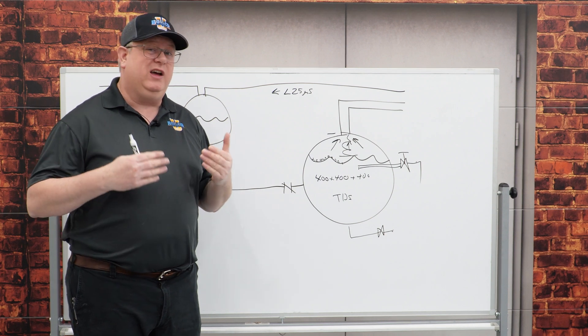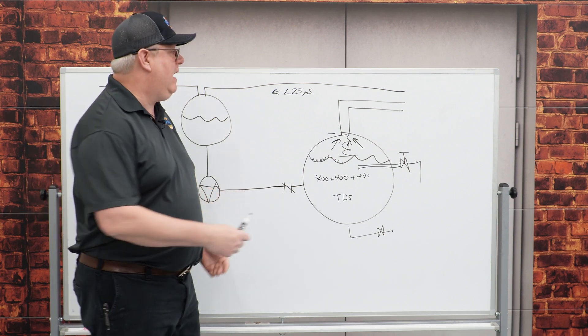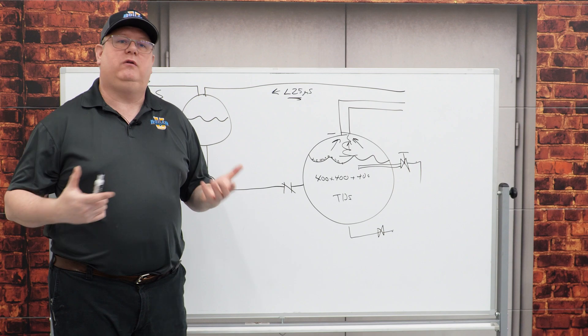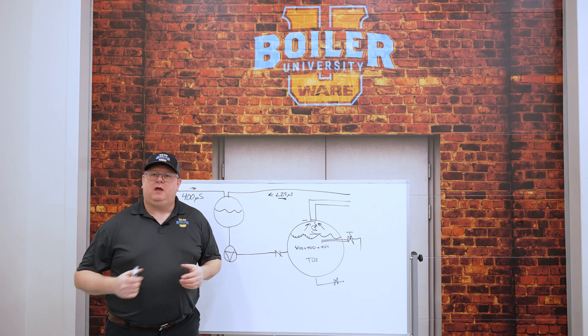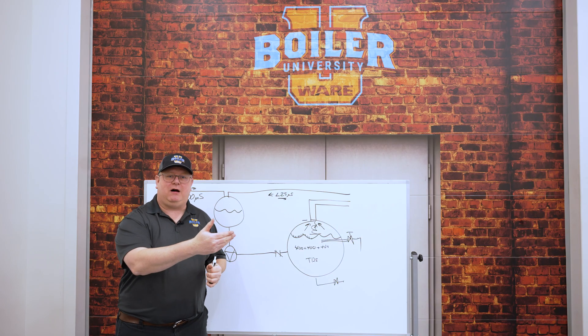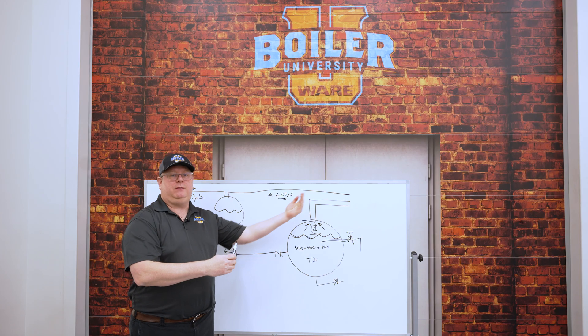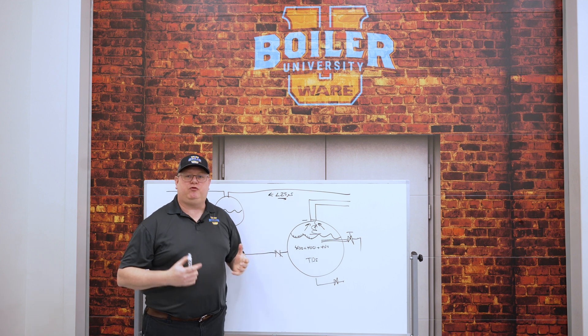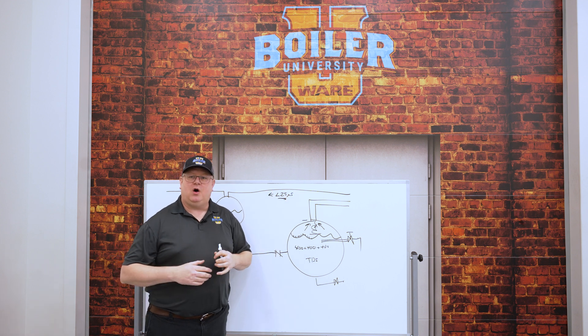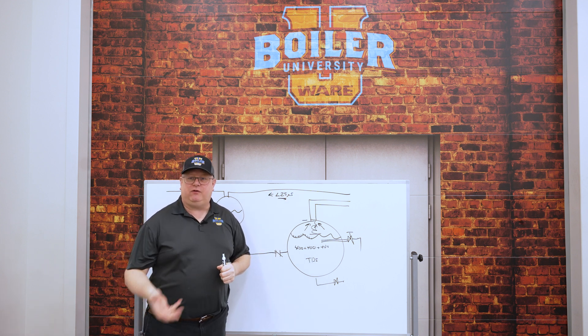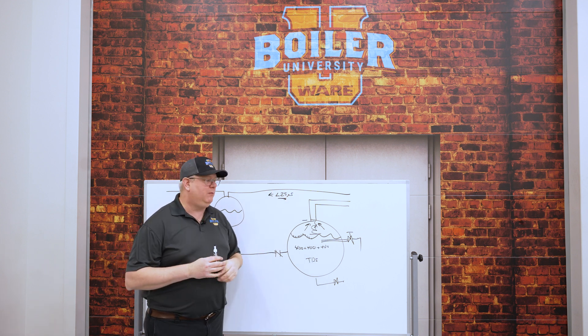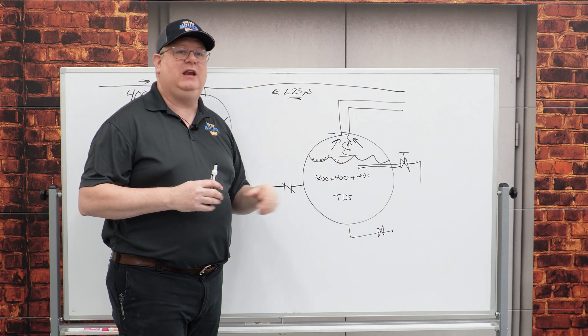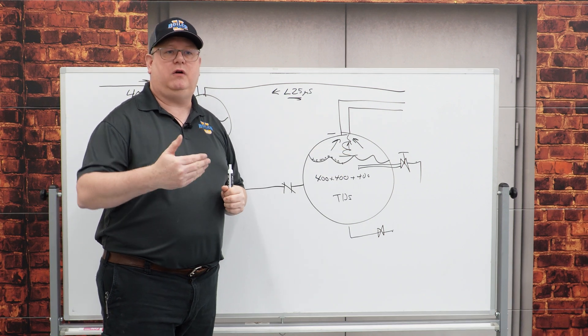A really easy way to test for that is to test the condensate return, because if we're carrying solids out, that's going to be coming back. Getting a sample from a drip leg or a condensate receiver out in the system — if we see that number spike, that's going to indicate that we have carryover.